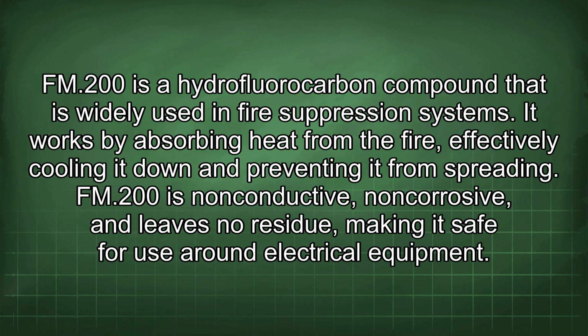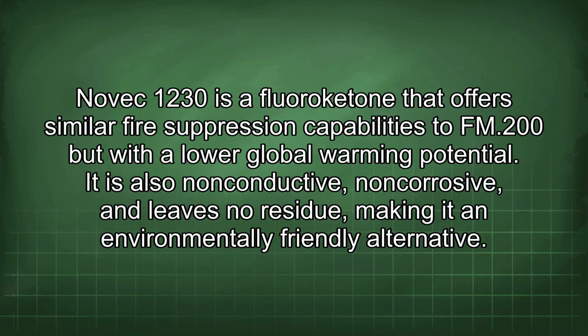FM200 is a hydrofluorocarbon compound that is widely used in fire suppression systems. It works by absorbing heat from the fire, effectively cooling it down and preventing it from spreading. FM200 is non-conductive, non-corrosive, and leaves no residue, making it safe for use around electrical equipment. Novec 1230 is a fluoroketone that offers similar fire suppression capabilities to FM200 but with a lower global warming potential. It is also non-conductive, non-corrosive, and leaves no residue, making it an environmentally friendly alternative.